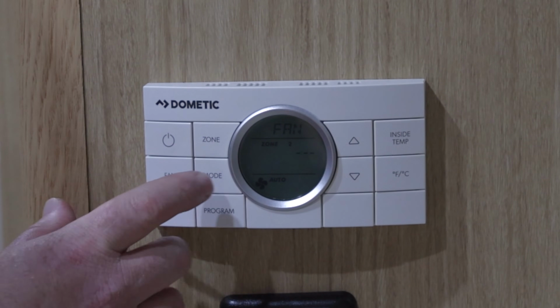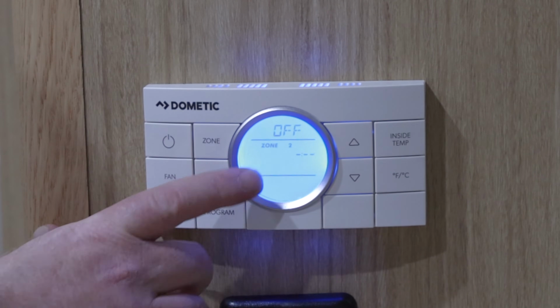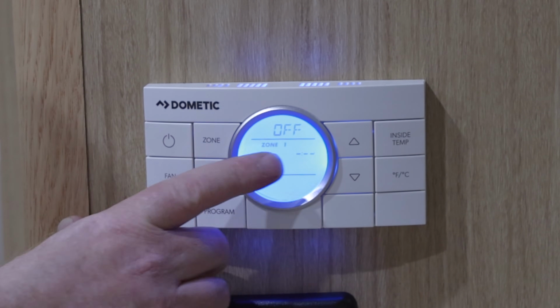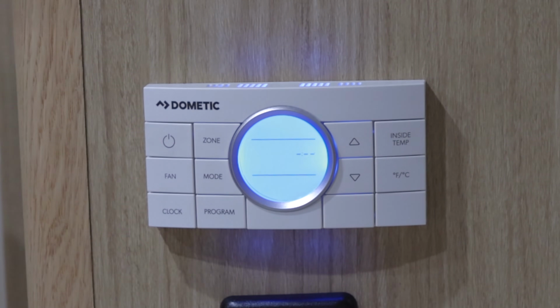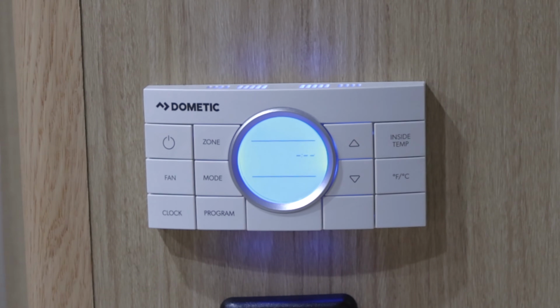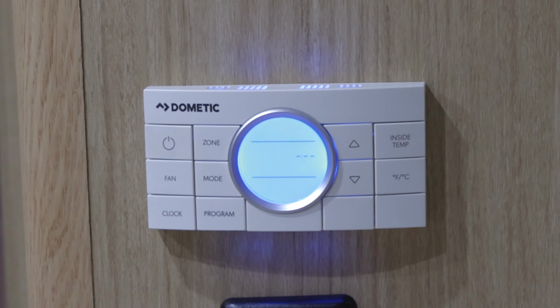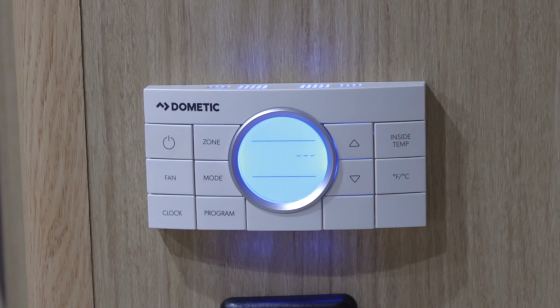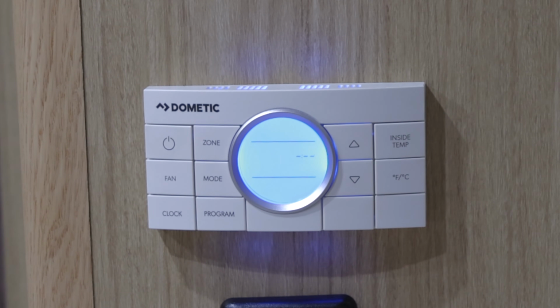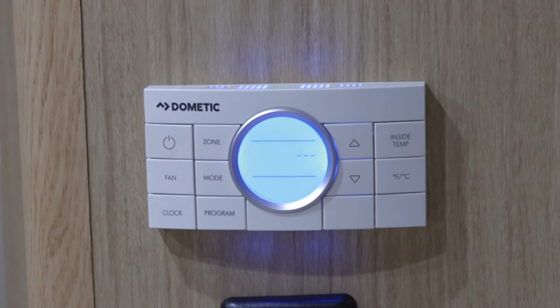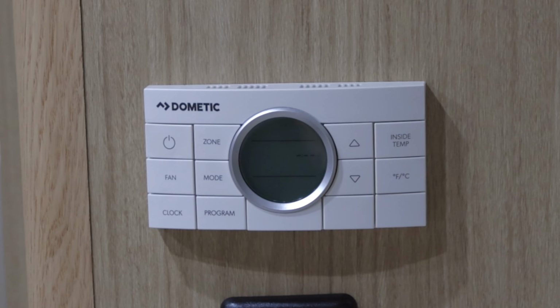It only works on low, medium, or high. Please make sure that when you're done, you cycle both zones all the way to off before you turn the control panel off, so that way when you turn the trailer on, the air conditioning system does not automatically come on. It only comes on when you come over here and turn it on yourself. And you'll notice when you turn the furnace off that it'll continue to run for about 2 minutes. You want to let that cycle complete before you depower the trailer so it has a chance to cool itself off. Thank you very much.